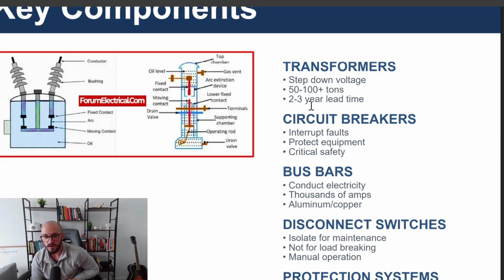There was an issue where a transformer was installed from China and it had something in it that really freaked out the U.S. government. The transmission operators, or the U.S. government, banned it for a little bit, then revoked it as a policy. But a lot of transmission operators kept the approved list they'd already developed. So just check with your transmission operator - they'll give you an approved manufacturer list for these transformers. Otherwise you don't want to bring one in and have it rejected.